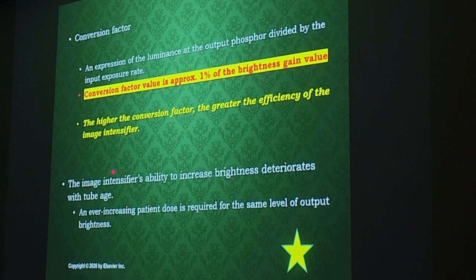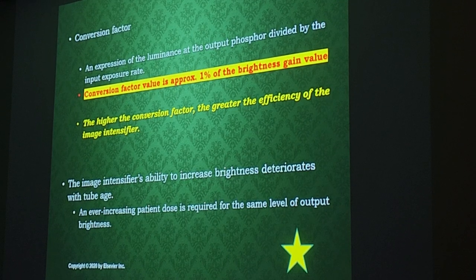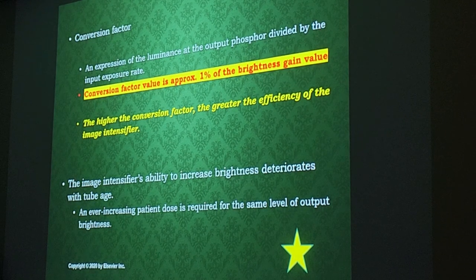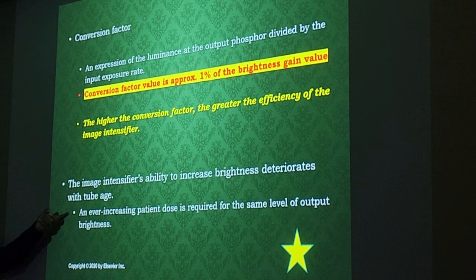The higher the conversion factor, the better the image intensifier is at giving you image intensity, so the higher the number the better the efficiency. As with any equipment, as it ages the quality goes down — so the image intensifier's ability to increase brightness goes down with age.